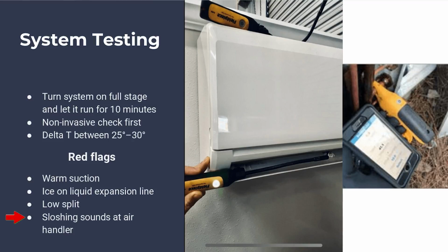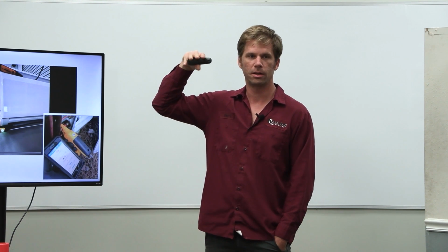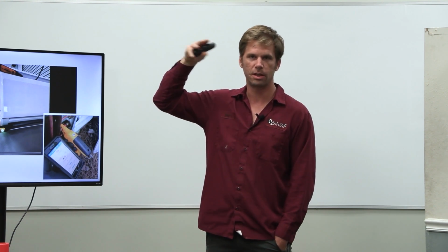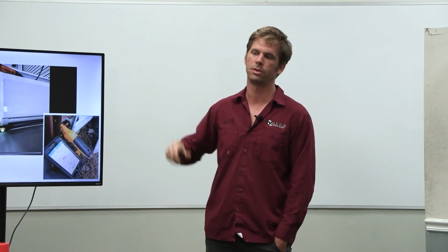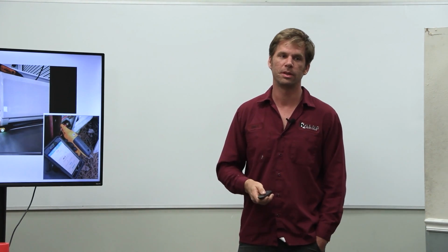Maintenance. Another sign would be sloshing sounds at the air handler. Not when you first turn it on, but when you're in there and you've turned on the system and you still hear this sloshing going on in the refrigerant, that is a typical indication that you are low on charge on that side of your system.